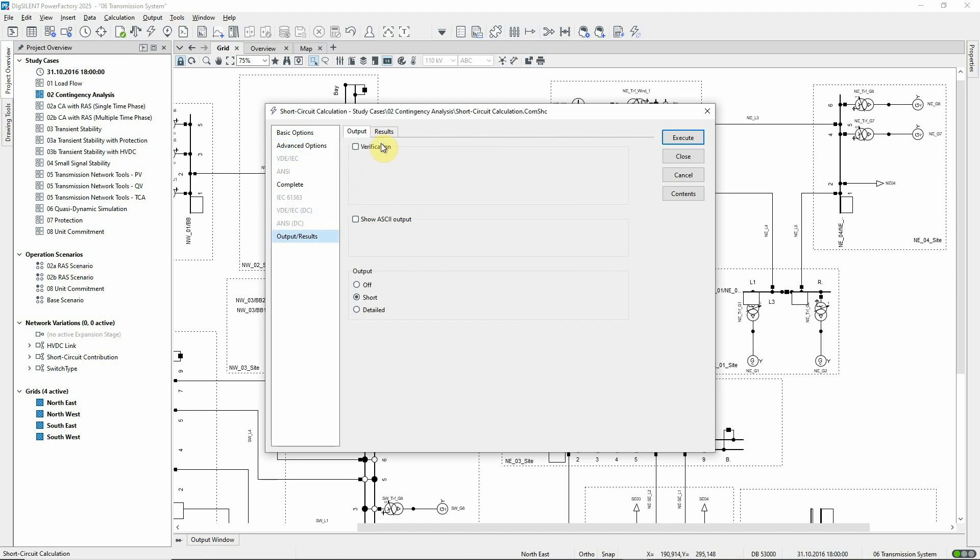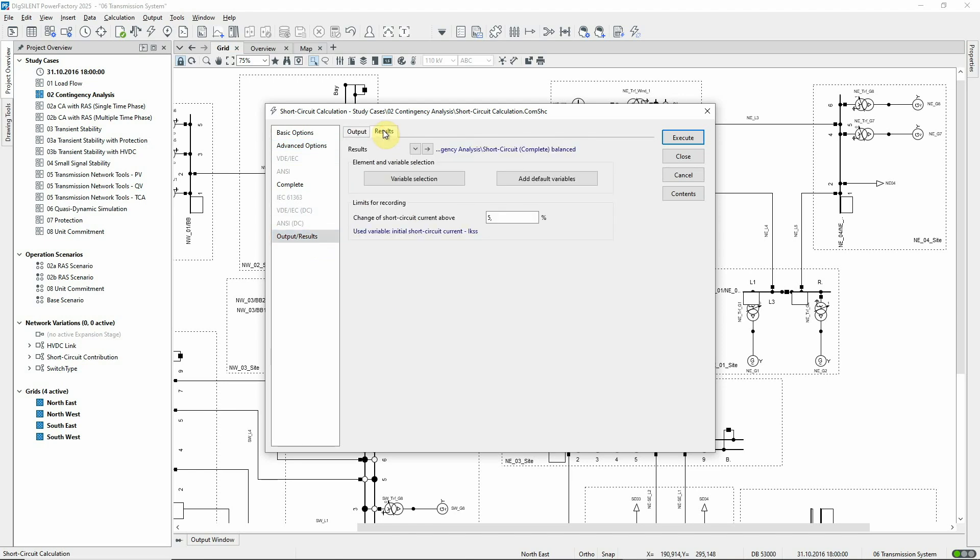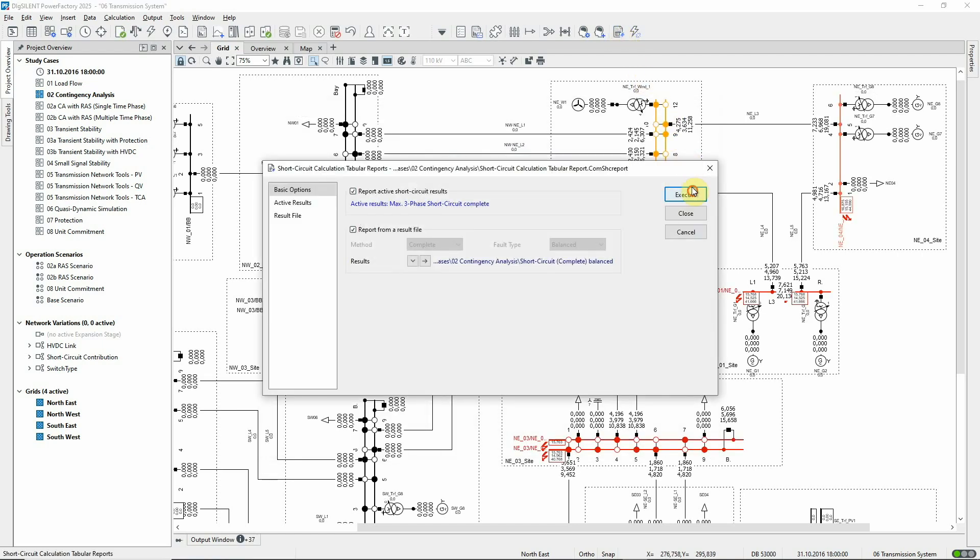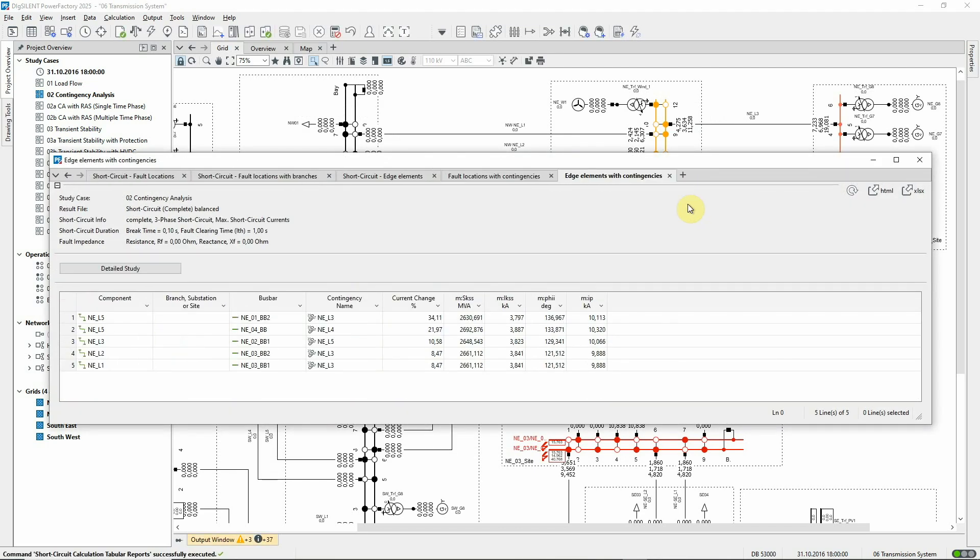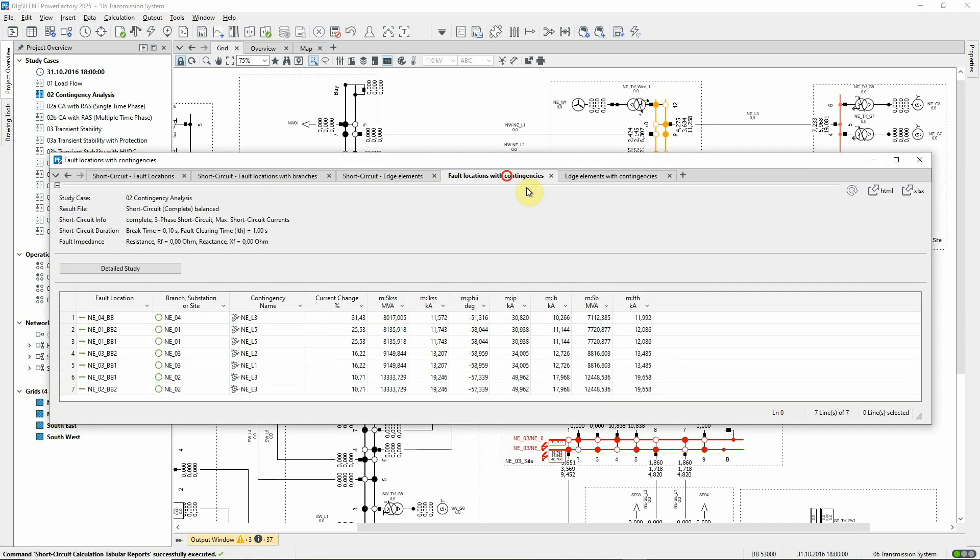The results are recorded in a results file, and can be limited according to the change in short circuit current for a contingency compared with that in the base case. Reports provide an overview of the results. For example, here we see, for each short circuit location, the contingency that results in the largest percentage change in short circuit infeed.